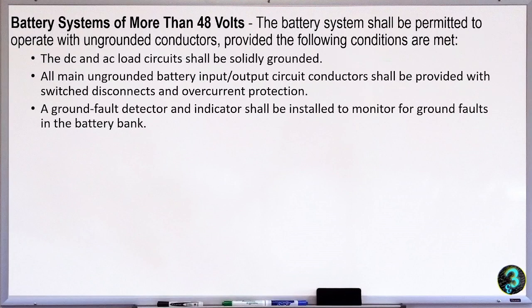So a battery system of more than 48 volts shall be permitted to operate with ungrounded conductors provided the following conditions are met. So this is for more than 48 volts. The DC and AC load circuits shall be solidly grounded. All main ungrounded battery input or output circuit conductors shall be provided with switch disconnects and overcurrent protection. A ground fault detector and indicator shall be installed to monitor for ground faults in the battery bank.